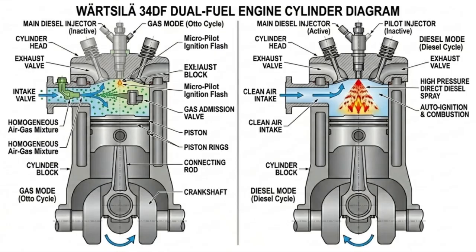On the left is gas mode, operating on the Otto cycle. Natural gas is mixed with intake air through the gas admission valve, while a small amount of pilot diesel initiates combustion inside the cylinder. On the right is diesel mode, operating on the conventional diesel cycle. In this mode, the gas system is isolated, and combustion relies entirely on direct diesel injection into compressed hot air. This dual-fuel configuration enables seamless fuel switching while maintaining reliable operation and high thermal efficiency. Next, we will examine how the engine automatically transitions between these operating modes during actual plant operation.